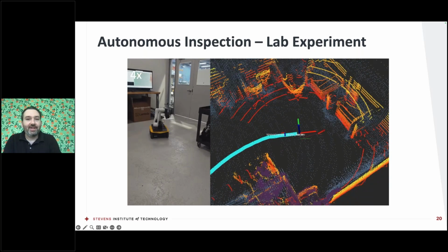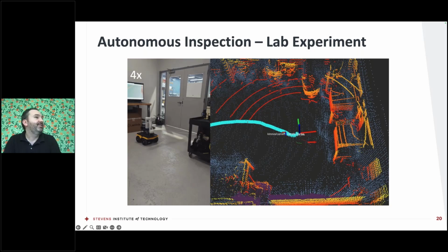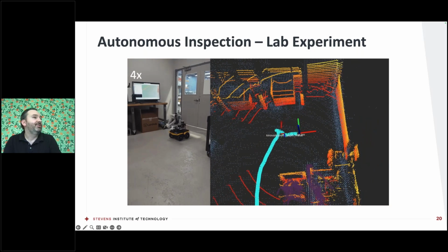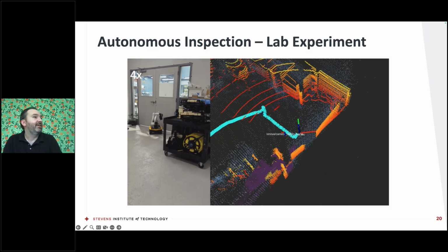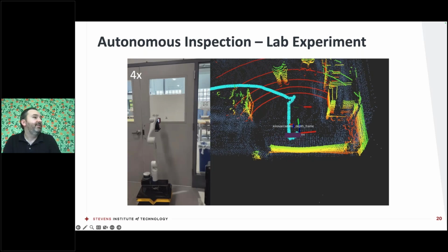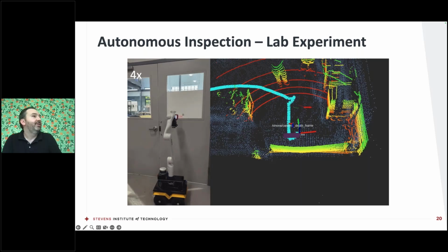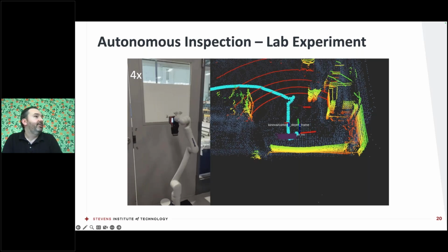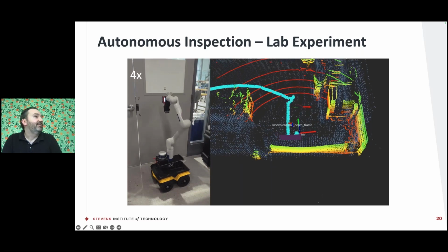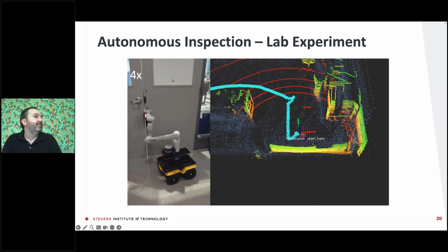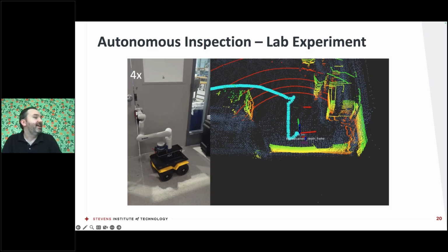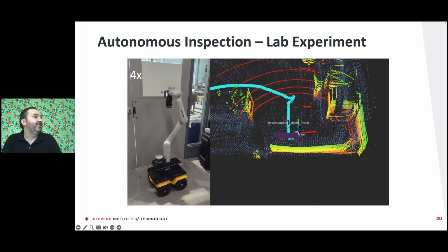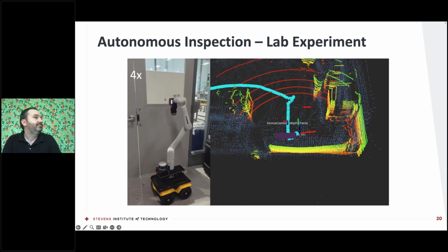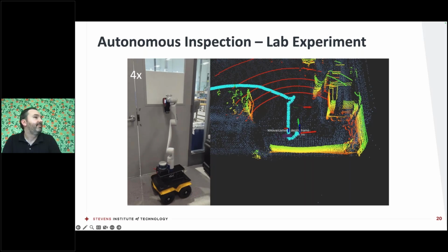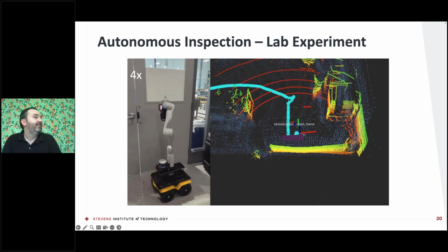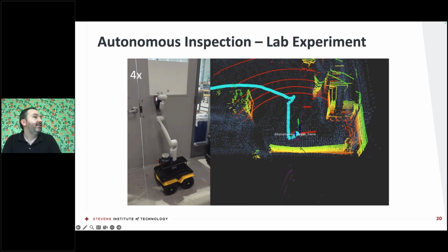Then it drives itself over to the second measurement location - another door, which we told it is a pothead compartment as well. The robot reaches the door location and drives close enough to make contact. It turns so the arm is aligned, then the arm makes a few adjustments. It identifies and scans a barcode, and begins collecting diagnostic measurements. First it takes the TEV measurement, requiring physical contact with the panel, scans the barcode again, gets a little closer, then collects the acoustic measurement.